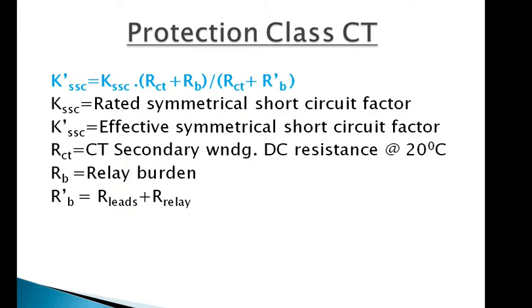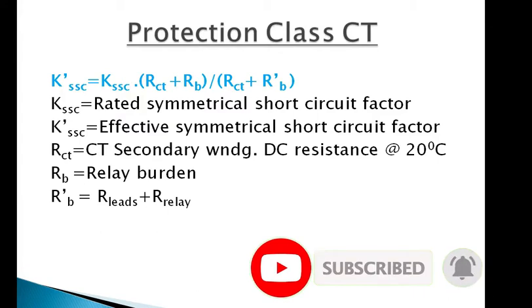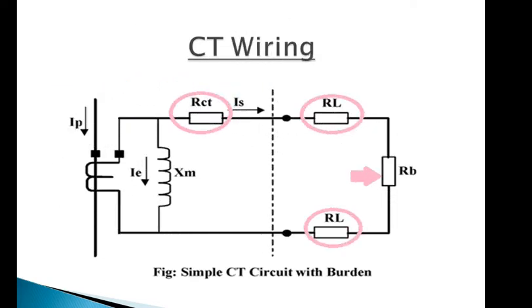Protection CT dimensioning is done as per the IEC formula: K'_ssc (effective symmetrical short circuit factor) equals K_ssc (rated symmetrical short circuit factor) multiplied by (R_ct + R_b)/(R_ct + R'_b), where R_ct is the CT secondary winding DC resistance at 20°C, R_b is the relay burden, and R'_b is the resistance of leads and relay.